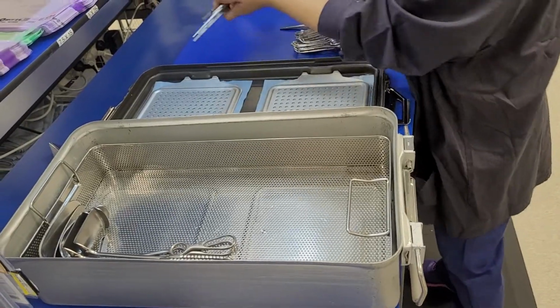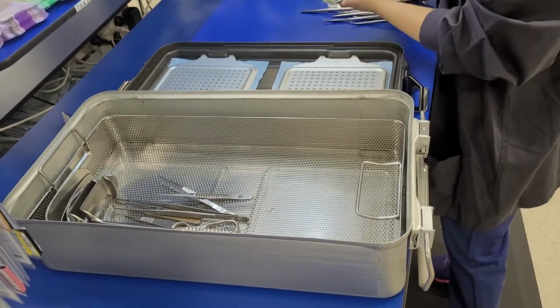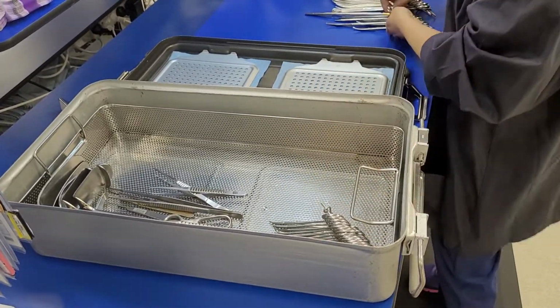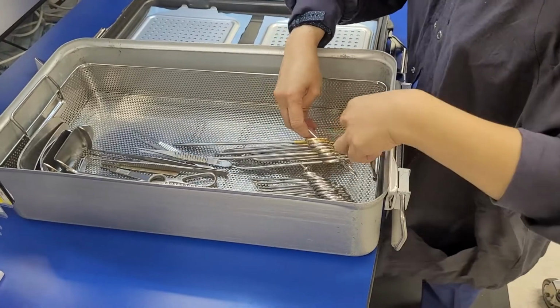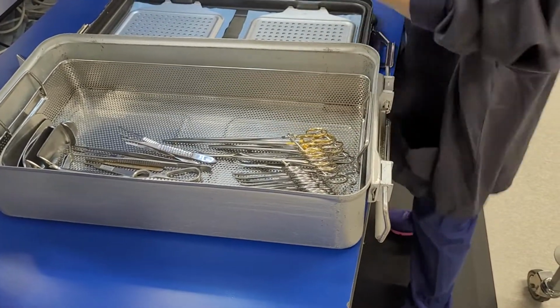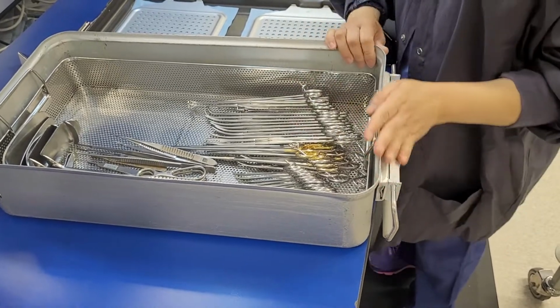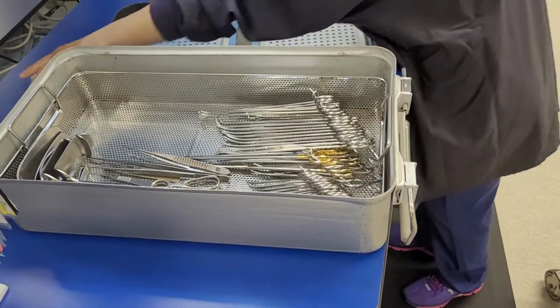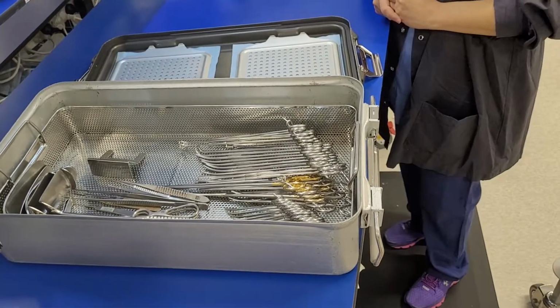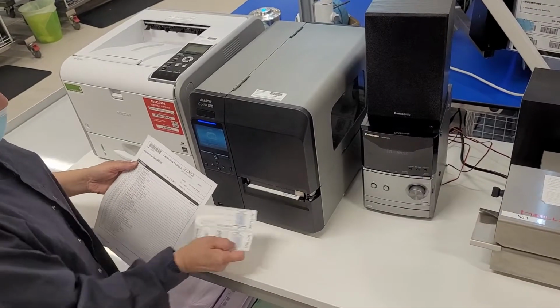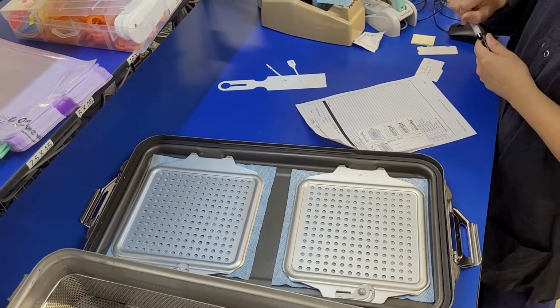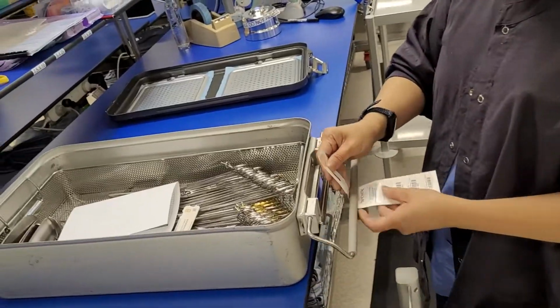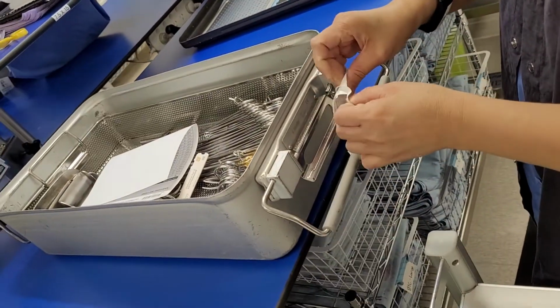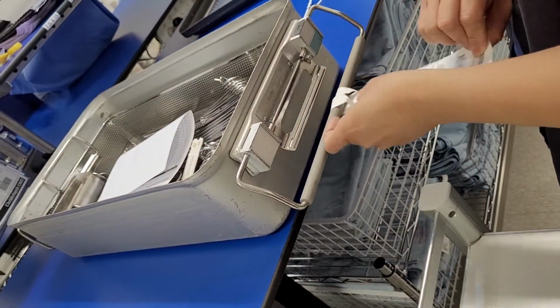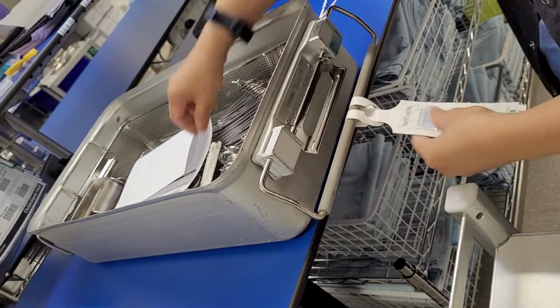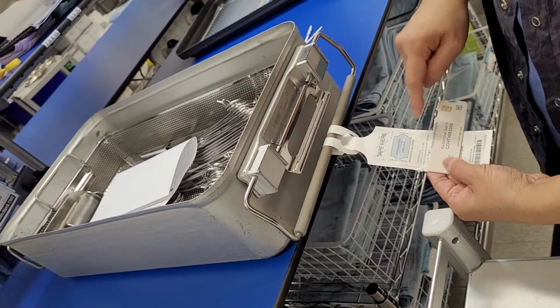After carefully inspecting every item in the prospective contents of a rigid container, it will be loaded into the container with all instrument handles facing in one direction, into an open position, to ensure direct contact with the steam during autoclaving. It is important that all instrument surfaces are exposed to the sterilizing action. Ensure that all relevant documentation is completed and has the correct identification of the contents. Contents with wrong or missing instruments could cause serious problems up to the point of use. If the procedure is done incorrectly, it could undo all the processing of RMDs up to that point.